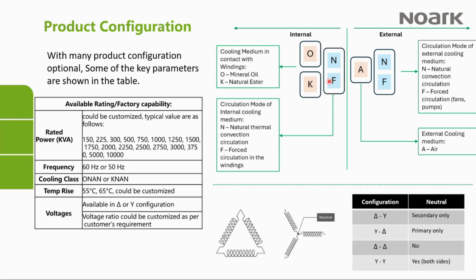In that case, we are not just relying on natural convection. We are using some sort of pump or fan to increase circulation to cool the transformer, whether through the cooling medium, which could be oil or it could be natural ester. So we're using some sort of equipment to force the air around the transformer or to force the oil around the windings in order to cool the transformer.